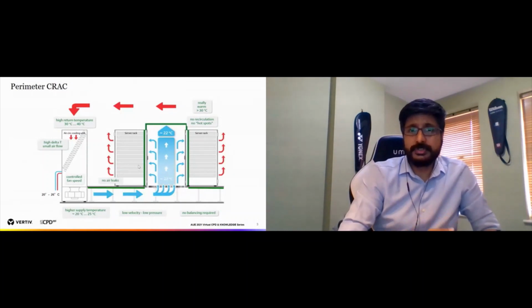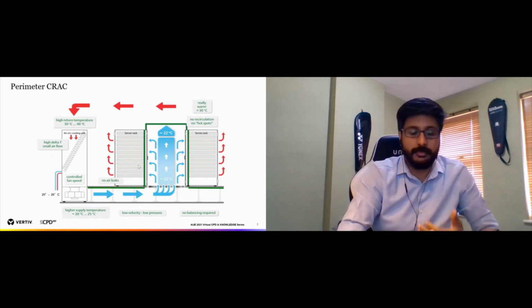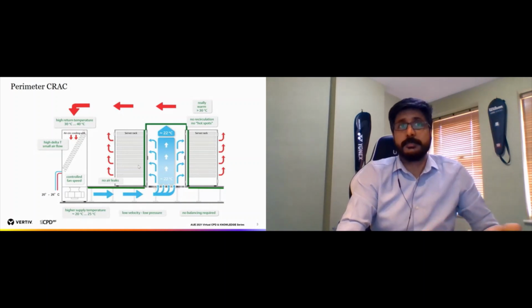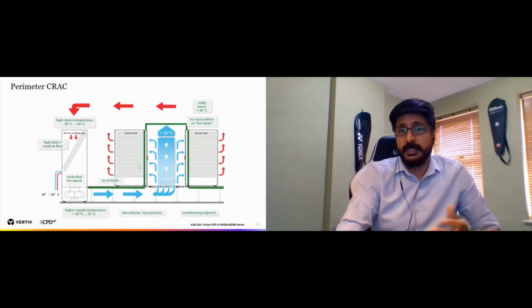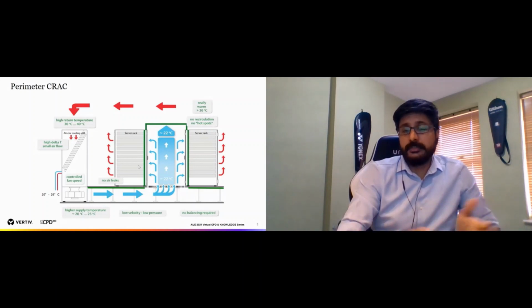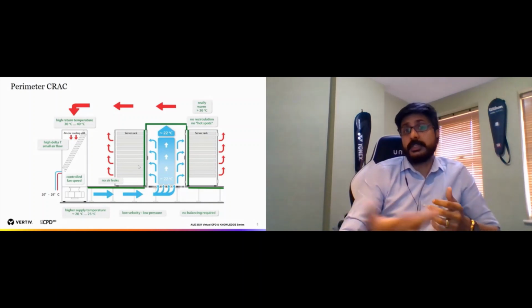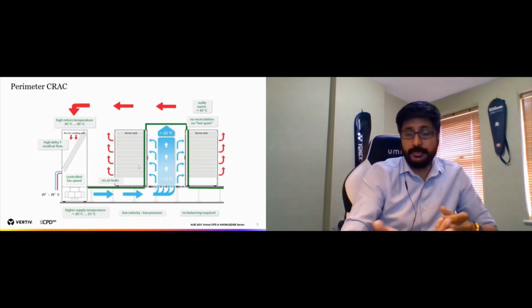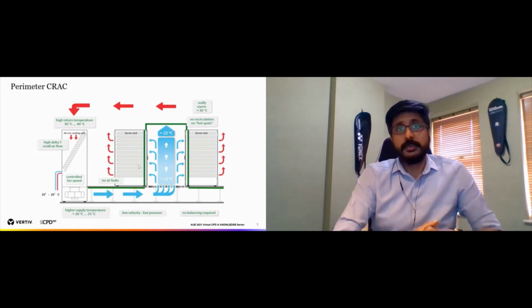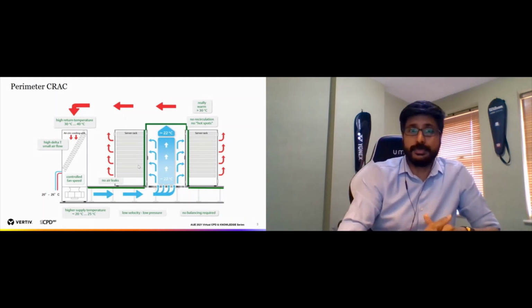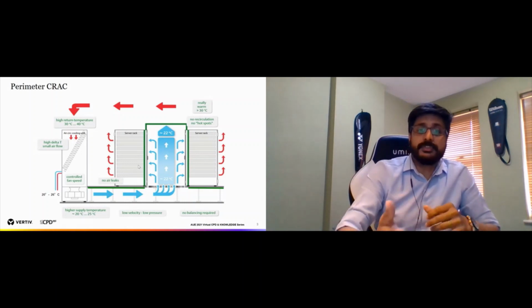To improve efficiencies, there was then the option of hot aisle containment or cold aisle containment. This prevented any mixing of air. The advantage was that we could raise the return air temperature coming into the CRAC units, which means we could have the same amount of cooling from a smaller footprint of units. The other option with containment was to increase the water temperatures if it was a chilled water cooling unit, which means we could have free cooling solutions coming in as well. So that's where the efficiency started coming in.